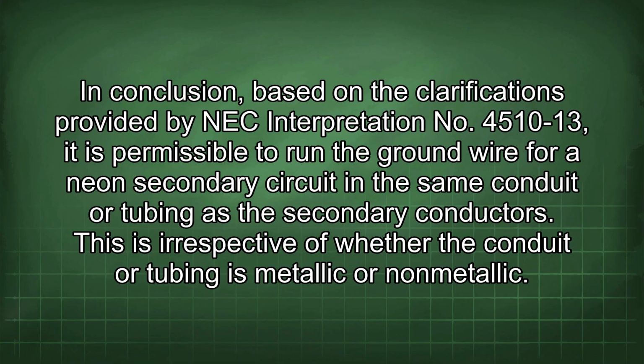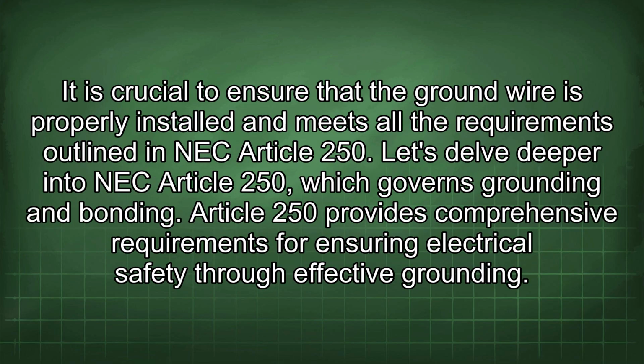In conclusion, based on the clarifications provided by NEC Interpretation No. 4510-13, it is permissible to run the ground wire for a neon secondary circuit in the same conduit or tubing as the secondary conductors. This is irrespective of whether the conduit or tubing is metallic or non-metallic. It is crucial to ensure that the ground wire is properly installed and meets all the requirements outlined in NEC Article 250. Let's delve deeper into NEC Article 250, which governs grounding and bonding. Article 250 provides comprehensive requirements for ensuring electrical safety through effective grounding.